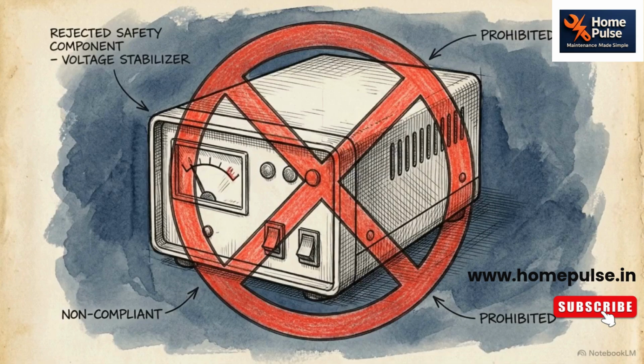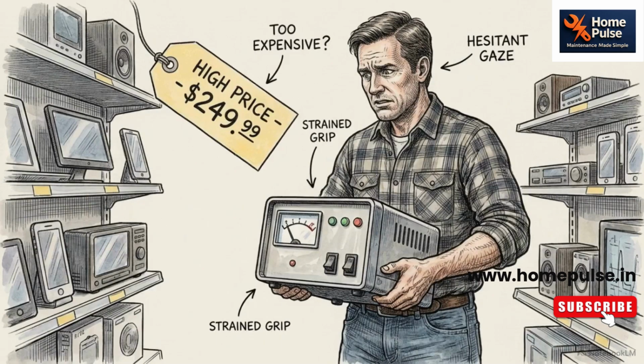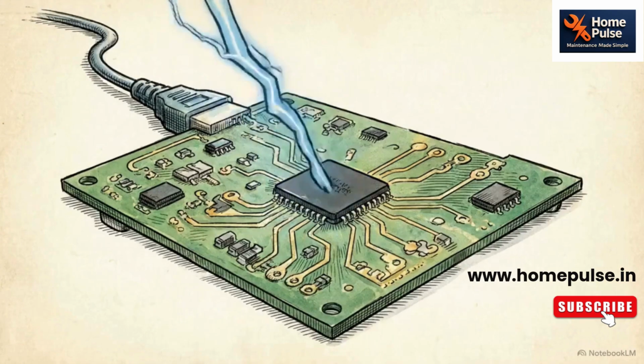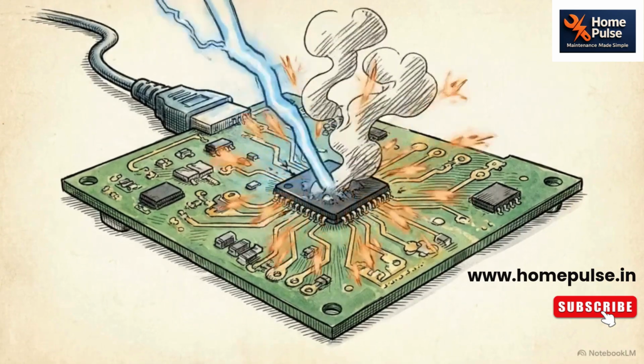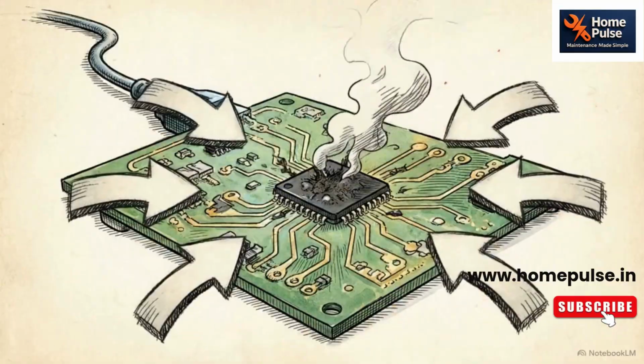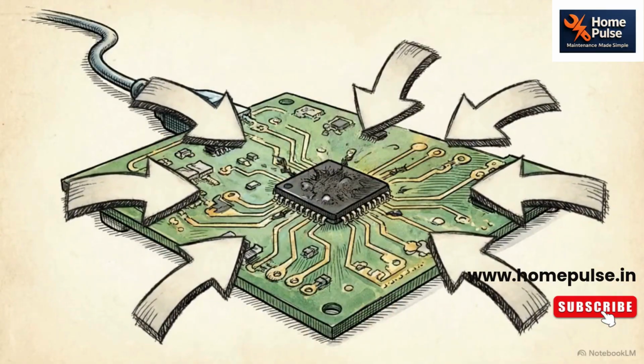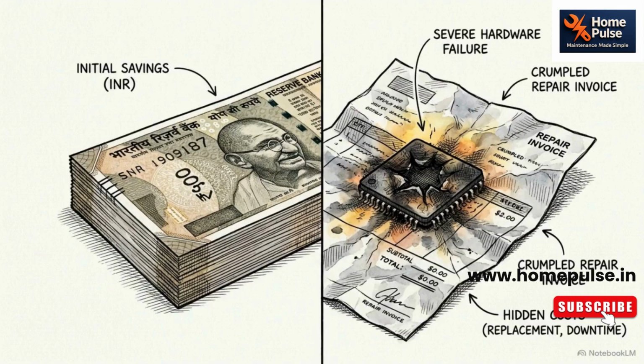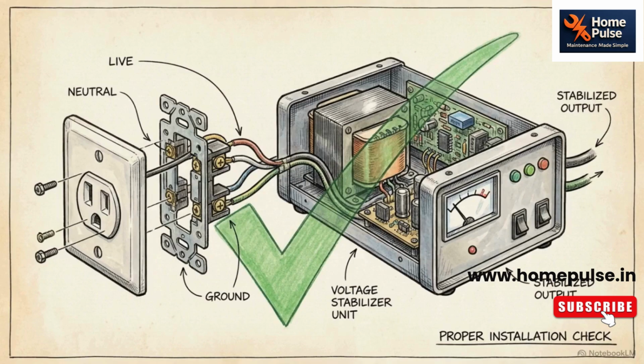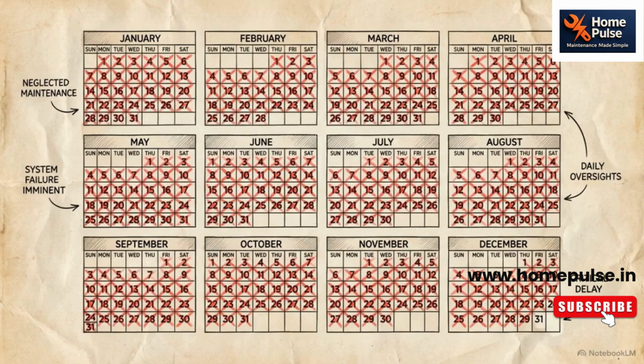The second electrical variable is skipping the voltage stabilizer. Many owners decide to keep 2,000 to 2,800 rupees in their pocket instead of buying a 4 kVA stabilizer. Without a stabilizer to absorb the shock, standard grid voltage spikes travel straight into the unit and instantly fry the sensitive printed circuit board. You keep installation costs low, but are effectively making a down payment on thousands of rupees in hardware replacement the first time the grid surges. Once the initial electrical setup is done, the next target for budget-conscious owners is the annual service fee, which usually runs between 600 and 1,200 rupees.